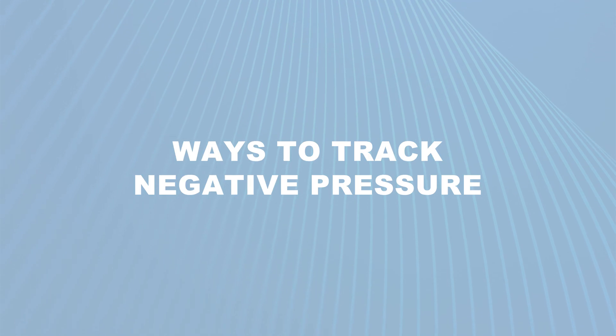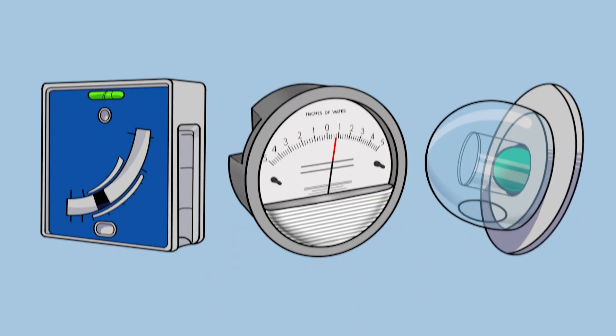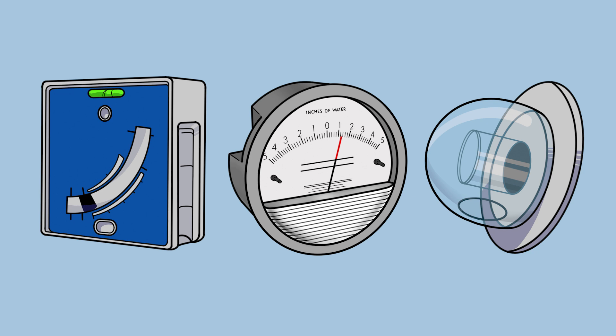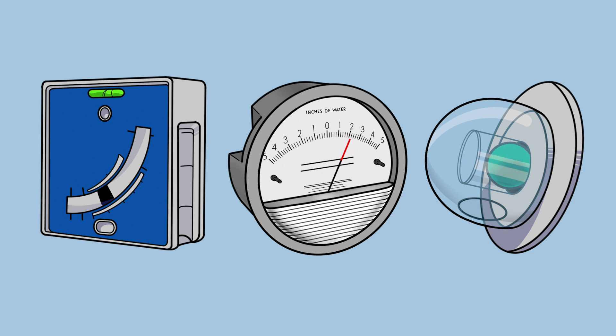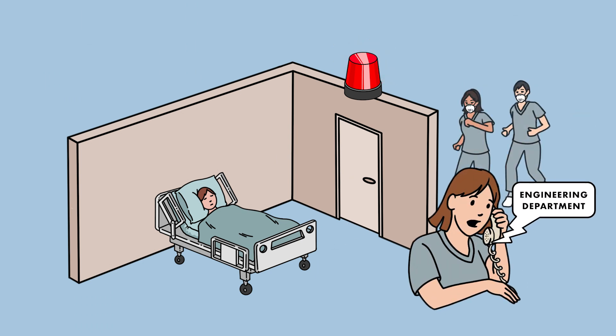There are several ways to track negative pressure. One way is through the building automation system using room pressure monitors. Other methods include local room pressure monitors, a manometer, or visual-based devices such as a ball in the wall. Whatever the method, it is essential to ensure that your staff is thoroughly trained on their role and knows what to do if a room shifts from negative to neutral or positive pressure.